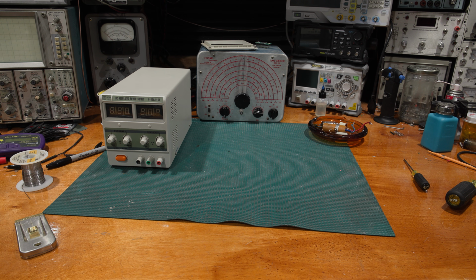That 5205 is a fixed, I believe it's a 100X amplifier. It's either a 100X or a 10X amplifier. I don't remember which one. I think it's a 100X because they use the 10 volt setting from the 5200A. So whatever goes into the front end gets magnified 100 times. So you put 10 volts in, you get 1,000 volts out. That amplifier is capable of doing 1,500 volts on the output peak to peak.